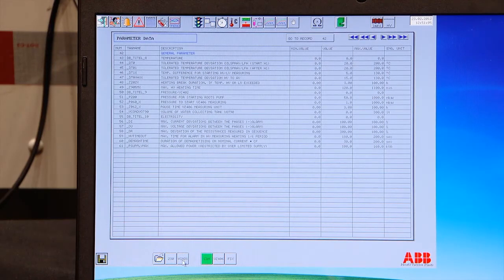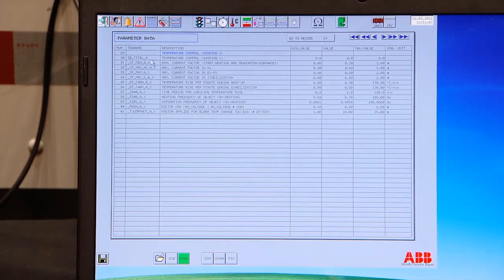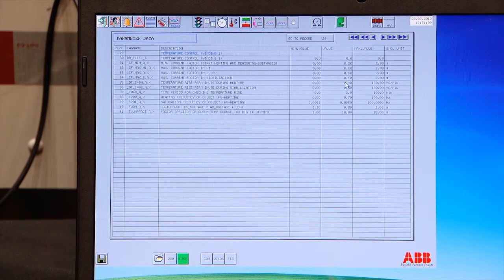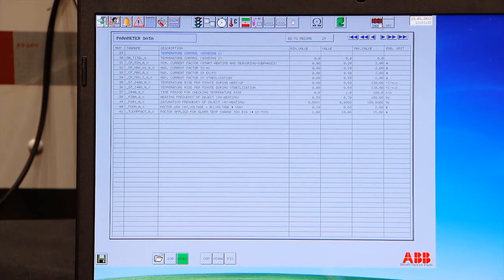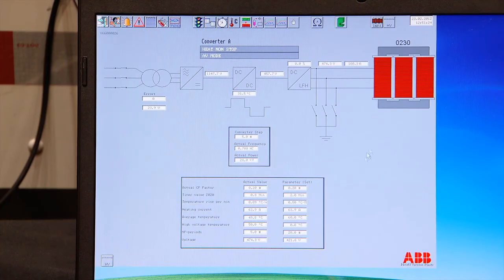Under windings, there is a parameter here. Temperature rise per minute during heating up, temperature rise per minute during stabilization. We keep that one at 0.5. Then we can go back to our converter overview page. We have this now changed to 0.5 degrees per minute.